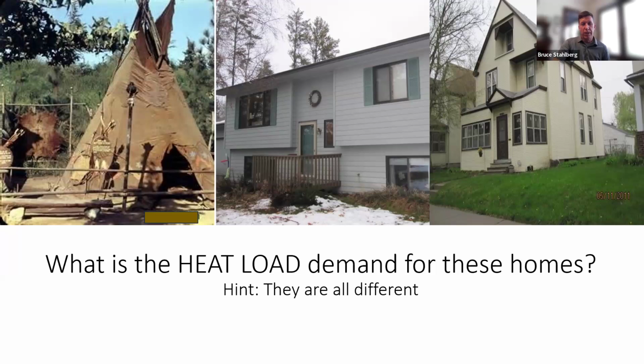Now, I have 3 different homes here. Obviously, they're all quite different, but each one of them would have a different heating load. Obviously, the one in the middle, kind of a split level rambler. The one on the far right looks like a 2.5-story old home. We should really be doing a manual J calculation to determine what size the systems would be.